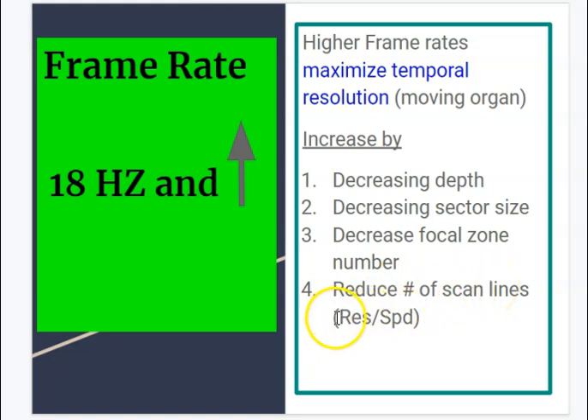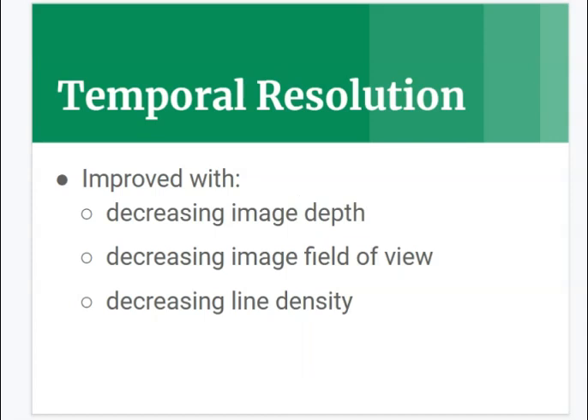And we have a function on our machine that I'm going to talk about in class. It's called the res speed function, and I'll show you how you use that. It definitely helps with temporal resolution by changing the number of scan lines. If you move towards this side, more scan lines; if you move towards this side, fewer scan lines. So again, temporal resolution improves with decreasing image depth, decreasing image field of view, and decreasing line density. Remember, if you decrease line density, you decrease resolution too. So there's a give and take here.